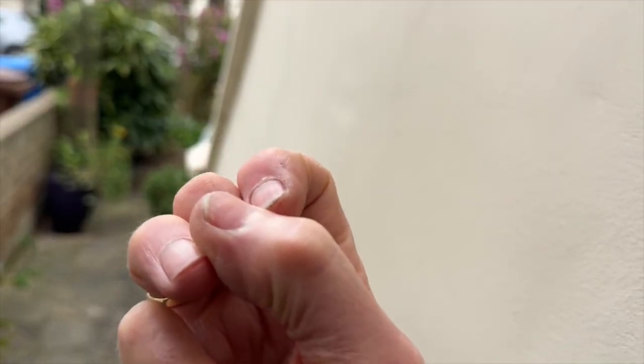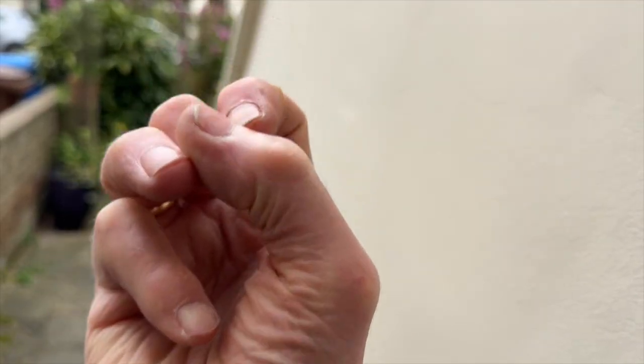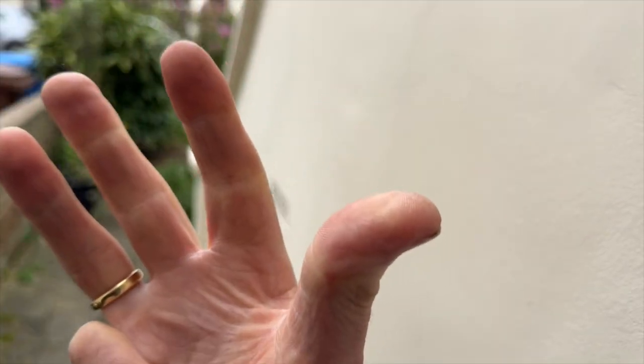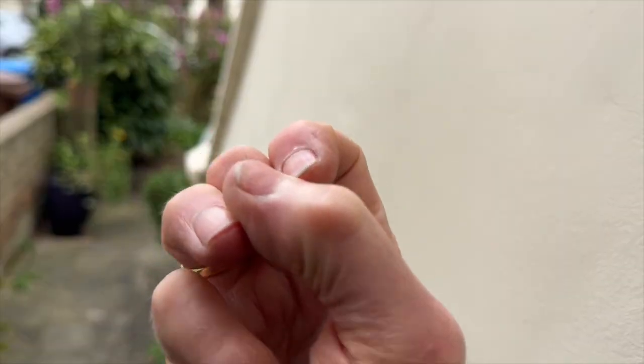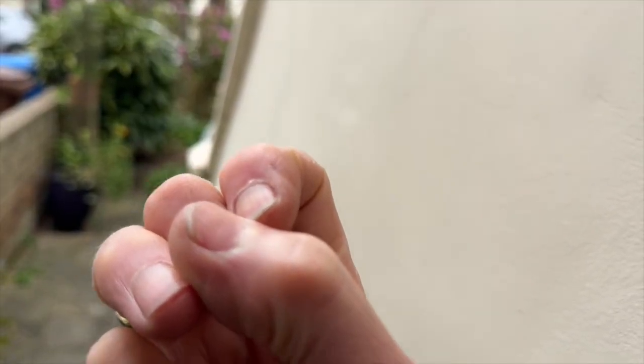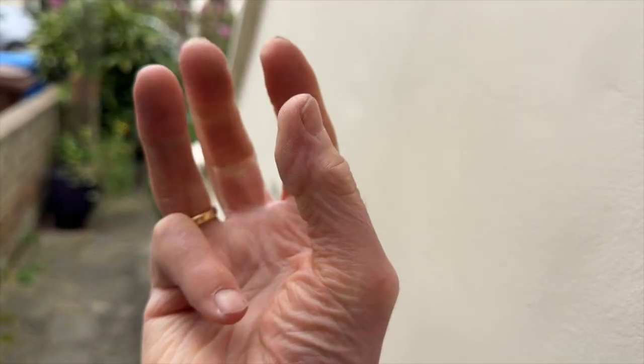Fans have a little flap at the back of the fan, and it's called a backflow shutter. It stops the air blowing back in. When you've got one of these, you don't need one of those. And the problem with those backflow shutters is they can get stuck quite easily and then force the fan closed, and it's just an extra thing in the way.